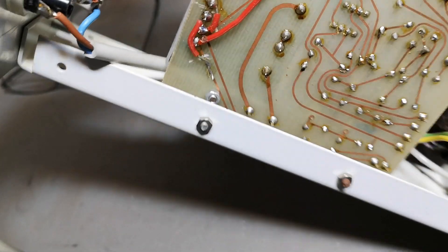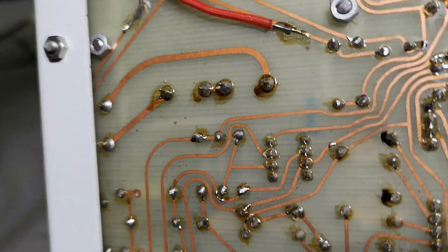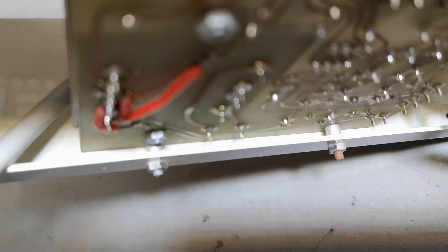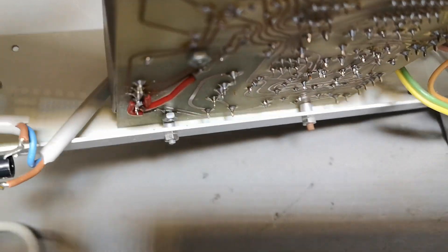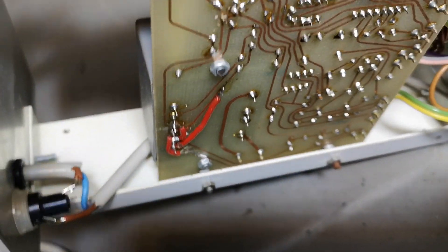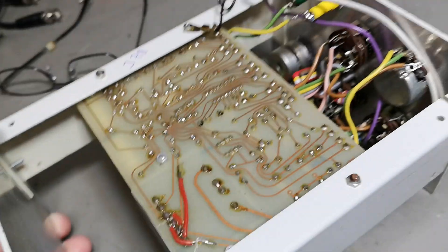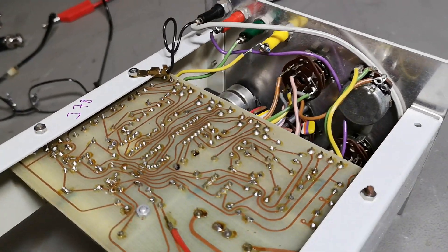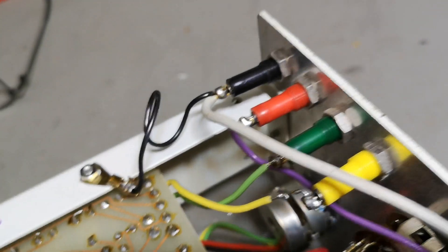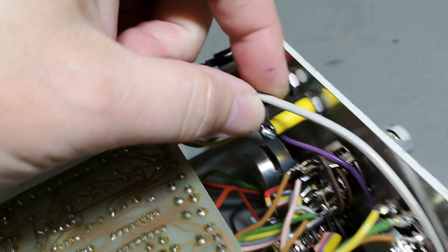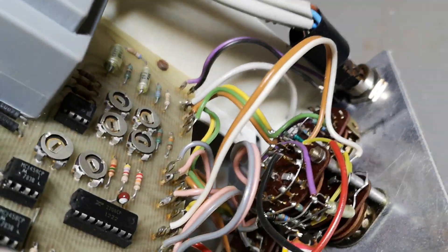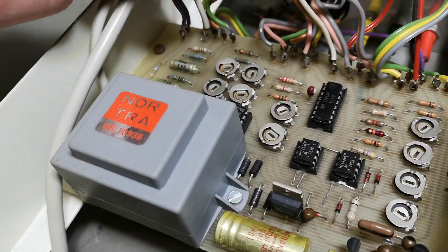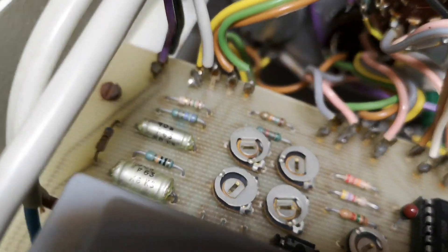This is on the secondary side, not the mains side. What do you think about the distance from mains to chassis? I think this is a little bit more than one millimeter, so this is not enough to pass the regulations we got today. And the chassis is also the ground output. There's a big fat wire for ground to the PCB.